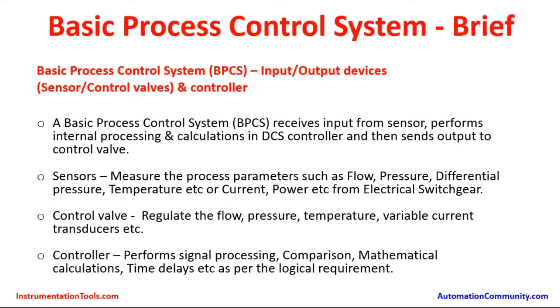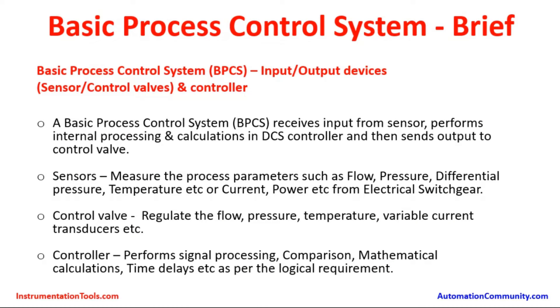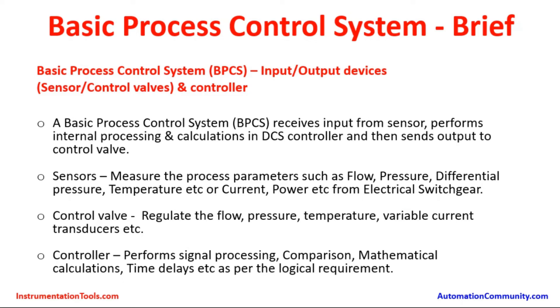Control valve: it is used to regulate flow, pressure, temperature, etc. Controller: this is the core topic. It performs signal processing, comparison, mathematical calculations, time delays, etc., as per the logical requirement. For each particular process there is a requirement developed by process engineers and chemical engineers during the design of the project. They formulate a control narrative based on which the logic controllers work and give the required command to the control valves to control pressure, flow, temperature, and other required process parameters.